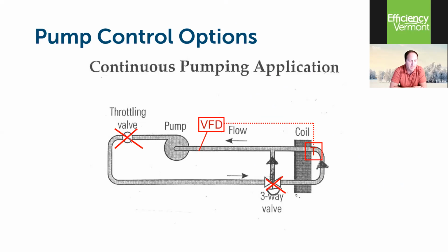When you're throttling a pump or a fan back, that pump or fan is still running at 60 Hertz. It still has a single speed that it can operate at. You're just sort of choking it back, and that's not inherently efficient. You're making that motor do more work than it has to. So when you put in a VFD on a pump or a fan, you can eliminate the throttling valve and the three-way valve because you can simply slow the VFD down to match the demand, whether it's heat, cool, air, exhaust, whatever it may be. We just simply slow the motor down.